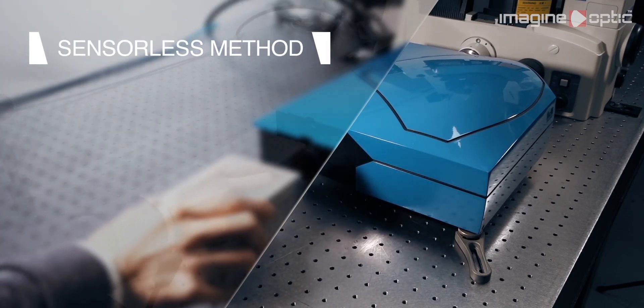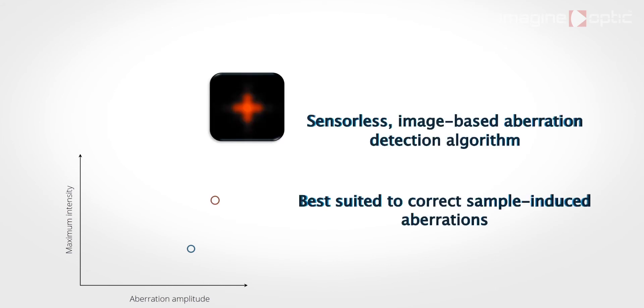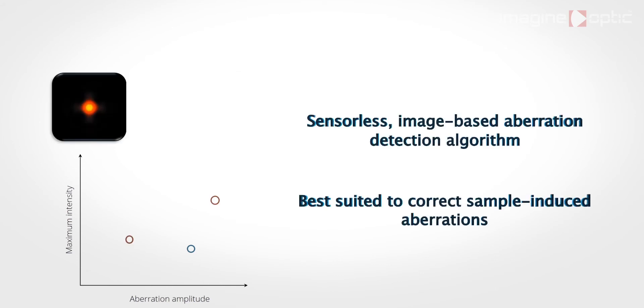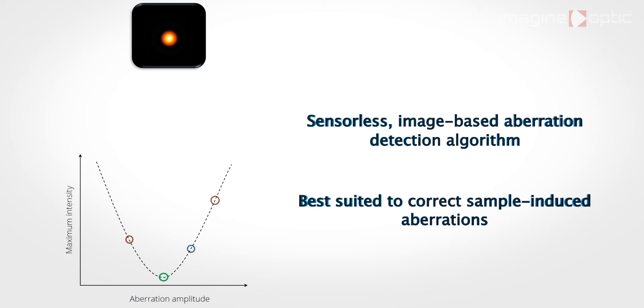To do so, we now replace the wavefront sensor by the camera and use an iterative image-based algorithm using images of a diffraction-limited bead. By applying a small quantity of specific aberrations, we can measure the quality of the PSF and determine which set of aberrations gives the best PSF.